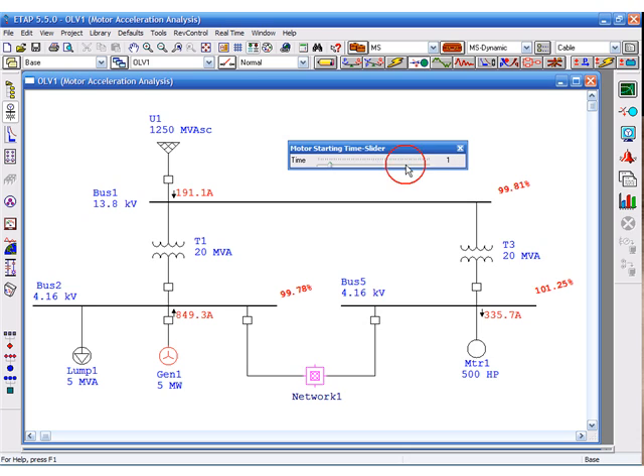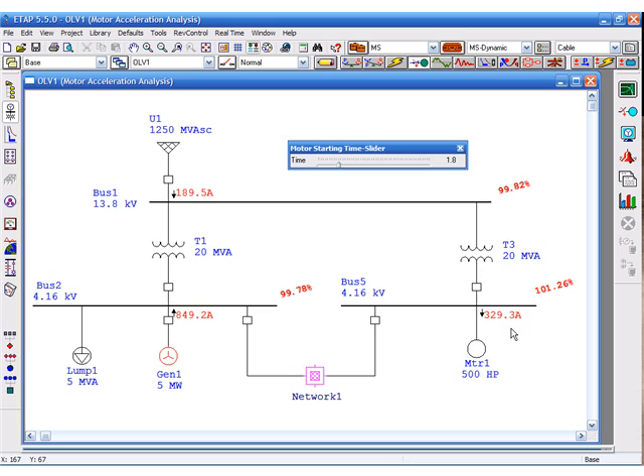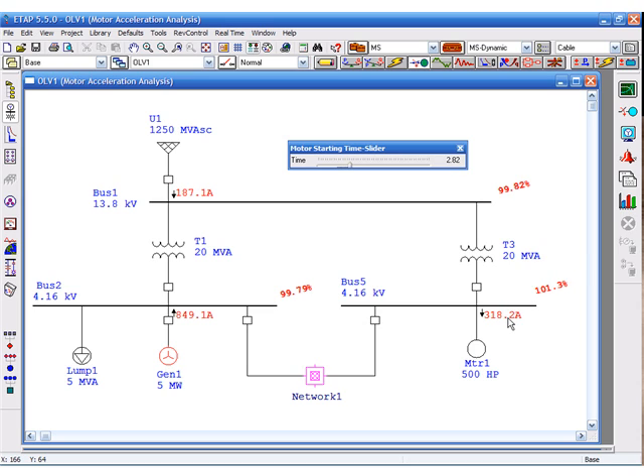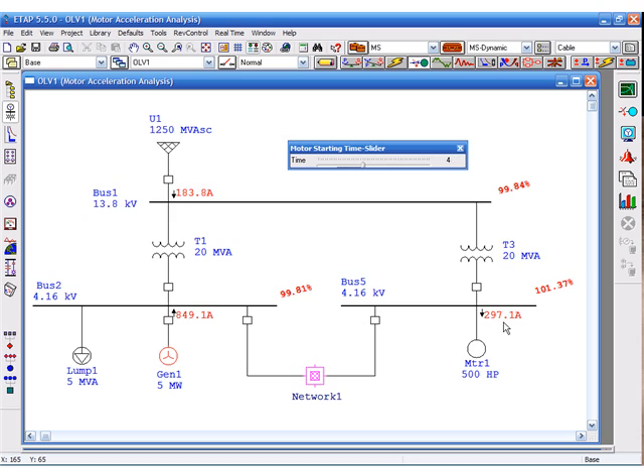T equals 1 second is where we accelerated the motor. Since this is a dynamic acceleration, you will see the locked rotor current slowly decaying as you move the motor starting time slider. Once the motor is close to rated speed, the locked rotor current will drop sharply and the motor will start drawing full load amps. At 4.5 seconds, this motor has started drawing full load amps.